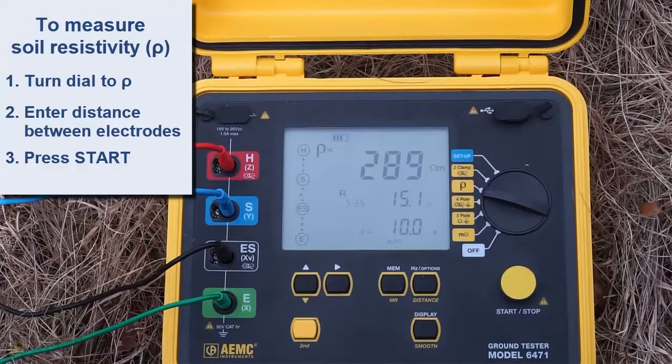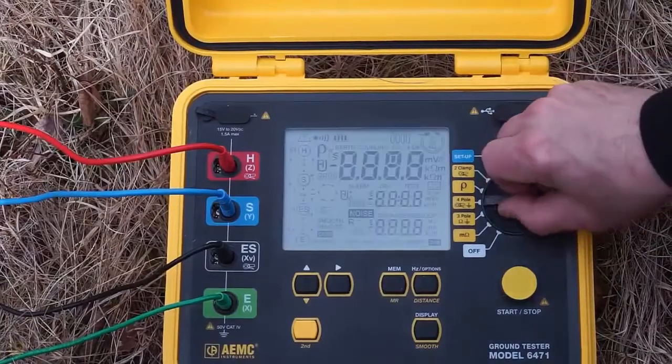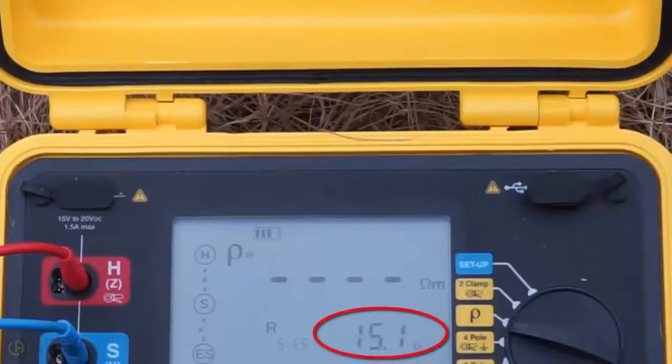This will save time and eliminate potential math errors. If your instrument doesn't offer automatic soil resistivity calculation, simply take a resistance reading. For example, if you don't enter the electrode distance, the ρ setting on the Model 6471 displays soil resistance, which as you can see is 15.1 ohms. We can now use this value to manually calculate the resistivity of the soil.